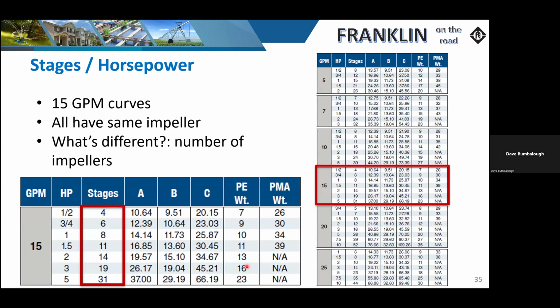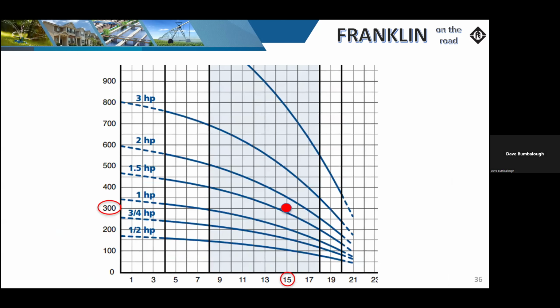Now, as we start trying to build more pressure, you'll notice that the stage count gets larger. And as it gets larger, meaning that we're trying to push more pressure, so does the horsepower. So the horsepower will climb as the stage or the length of the pump grows. We are trying to push a certain amount of volume to match a certain pressure or head requirement for that application. Now, once I start looking at sizing this system, I've picked the 15 gallon per minute. And as you can see, I've gone up the left-hand side of the scale, which is our TDH. I've brought it across till I hit my 15 gallon per minute intersection. And I noticed that it's really close to the 1.5 horse.